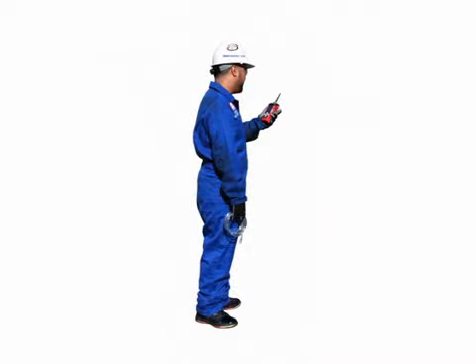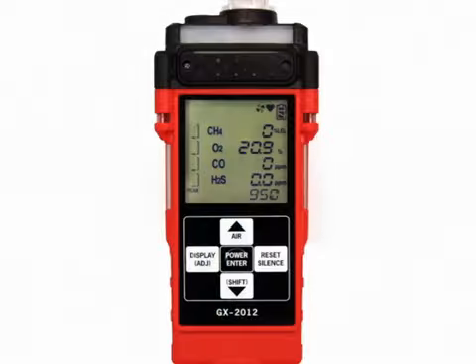There are three issues to keep in mind when monitoring for combustible gas. If your GX-2012 is equipped with both combustible sensors, then the % LEL sensor will be exposed to combustible gas concentrations above its working range during monitoring and calibration. The GX-2012 provides the % LEL sensor with protection against exposure to high levels of combustible gas.